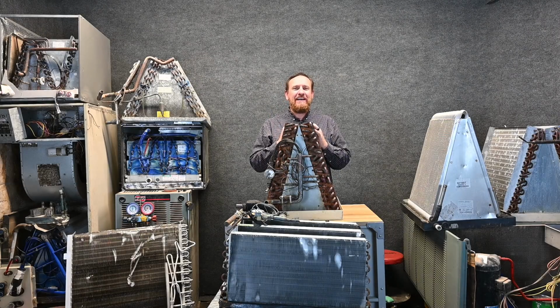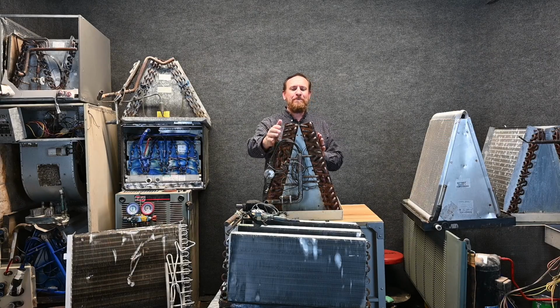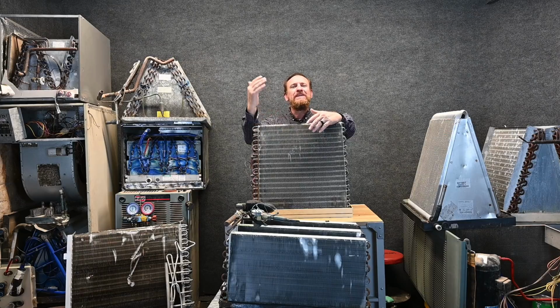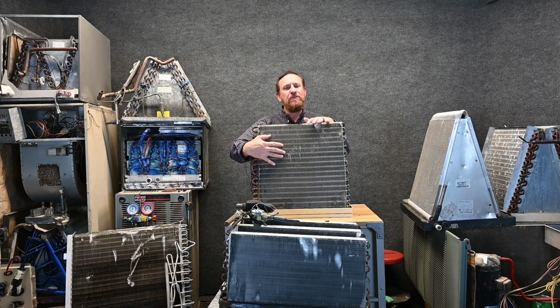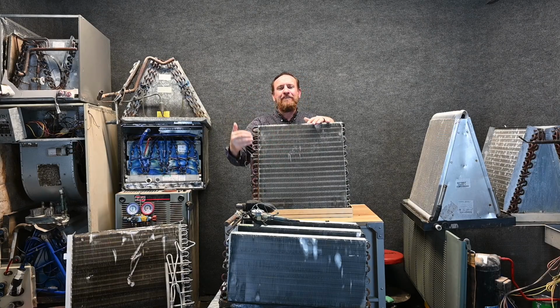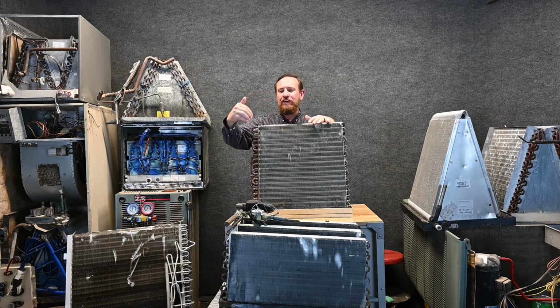On the air side though, and we're talking about air conditioning on this, the air side's a little bit different. On the air side, we have two things going on. One, we are sensibly cooling the air. Our thermometers, we can see a temperature change. So as the air travels through this evaporator coil, through these fins, it's warm, and that refrigerant's a lower temperature. So the heat leaves the air and transfers to that refrigerant that's boiling or changing state.